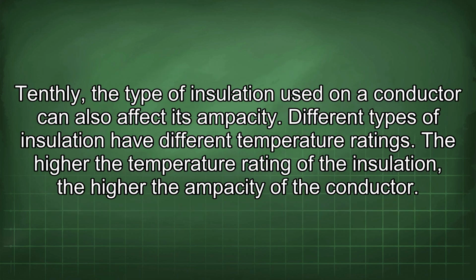Tenthly, the type of insulation used on a conductor can also affect its ampacity. Different types of insulation have different temperature ratings. The higher the temperature rating of the insulation, the higher the ampacity of the conductor.